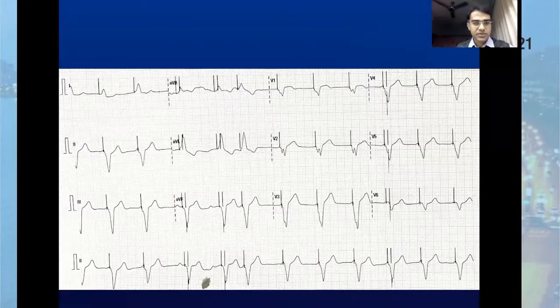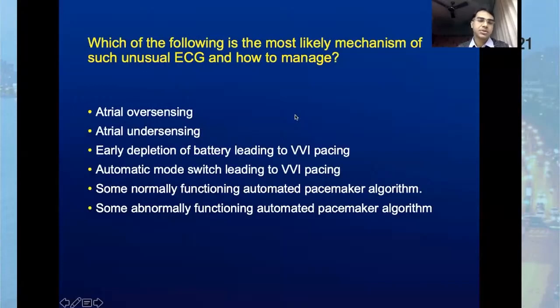When you look back at the initial ECG, although it appears that there is a pacing spike looking like VVI pacing, almost all the beats except these two beats have a P, and immediately after a P there is a pacing spike. So the pacemaker was possibly functioning in a dual chamber mode, but the AV delay was very short, except in these three beats. We'll be discussing in detail what those beats could be. Our usual differential diagnosis was maybe there was some atrial lead sensing issue, but had it been atrial oversensing, we thought there would be erratic ventricular pacing. This was not the case because there was consistent V pacing after a P wave. Secondly, there was no atrial undersensing either. In that case, we could have expected unnecessary atrial pacing spikes, which was again not the case.